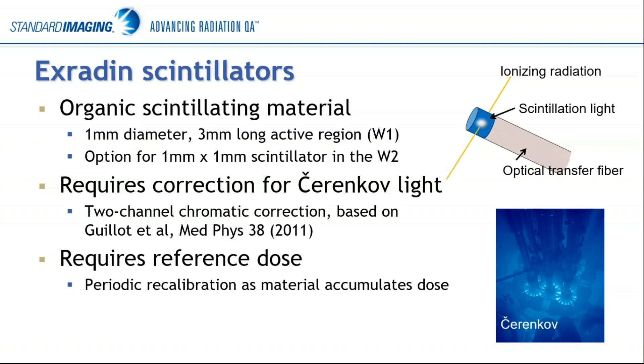The construction of our scintillators: we have an organic scintillating material with our W1 scintillator, which was the first generation. It's a one millimeter diameter, three millimeter long active region. With the W2, there's the 1x3 and an option for a 1x1 scintillator. These are coupled to a PMMA optical transfer fiber that takes the light to an optical collection system and converts it into electrical signal.